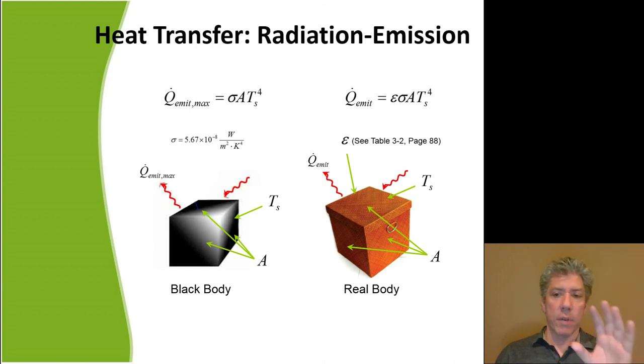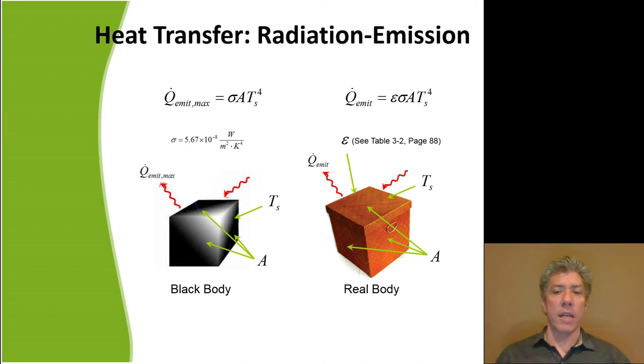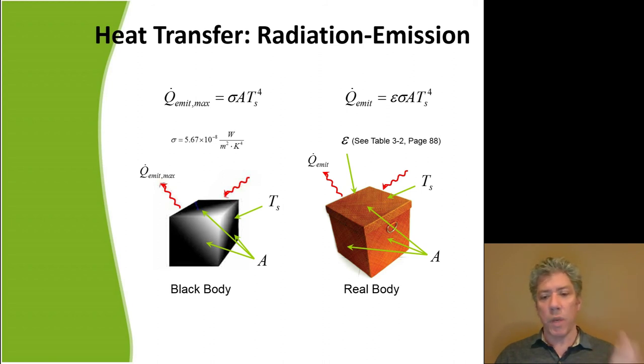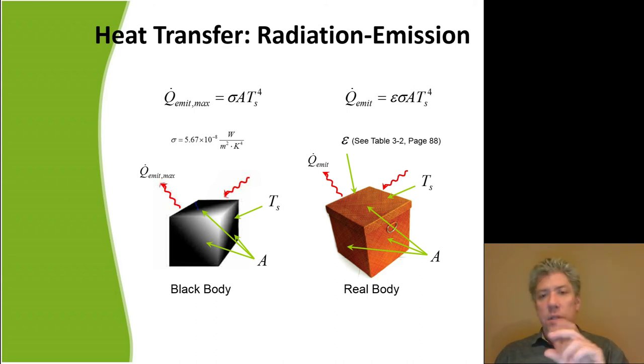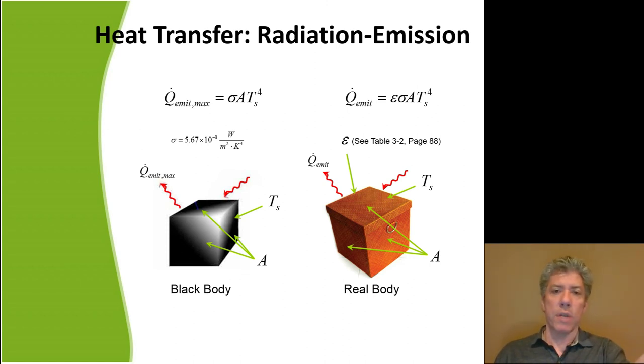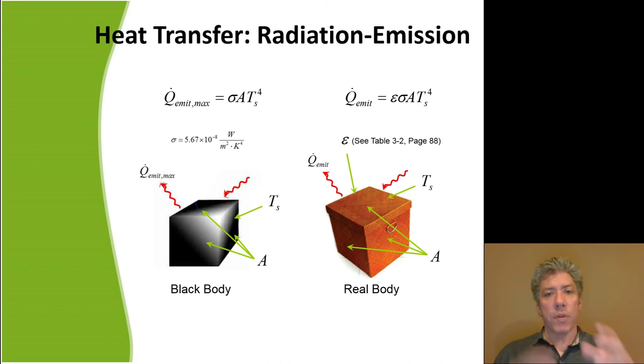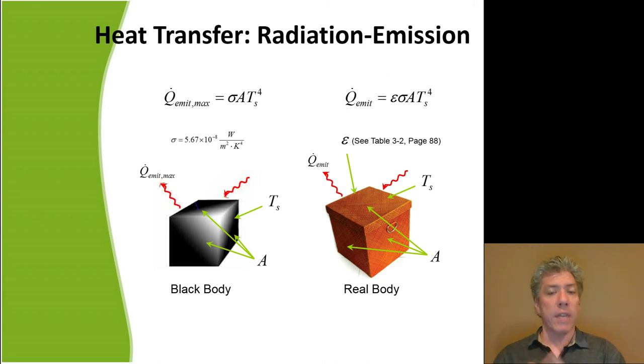I also decided to measure the outside temperature of the pipe. I got myself a cheap infrared thermometer from Harbor Freight for about $20. It senses infrared radiation and from that, using some assumptions, back-calculates the temperature. It basically uses the Stefan-Boltzmann equation in reverse — it measures the heat transfer rate it's sensing and back-calculates the temperature. But real bodies do not emit radiation at as high a rate as you'd expect given their temperature.